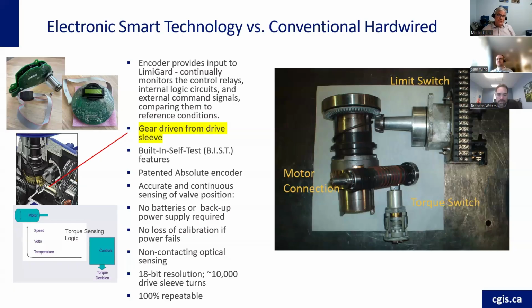What Limitorque developed way back was the absolute encoder. So even if you shut the actuator off, go on site, let's say you lost your power and you went to manually close the valve, when the power comes back up, it will know where it's located. It will know, hey, I've been opened another 20% or 30%. So it can pick it up from there and go open, go close, or go to a preset condition that we should be at when the controls come up.